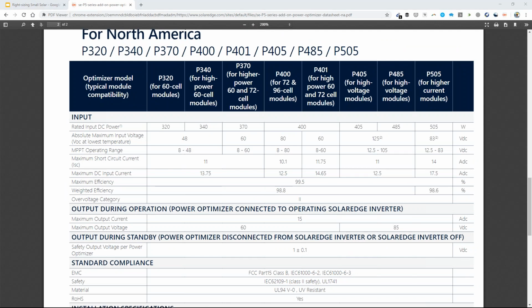On their spec sheet we get the power outputs of the optimizers and the input voltages of the optimizers. The 72 cell optimizers have higher input voltages than the 60 cell only optimizers, and that's why if you plugged a 72 cell module into a 60 cell optimizer, its voltage would be too high for its electronics and it would pop, meaning it won't work anymore.